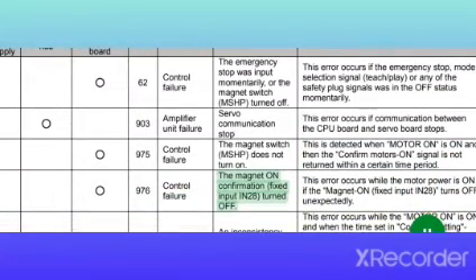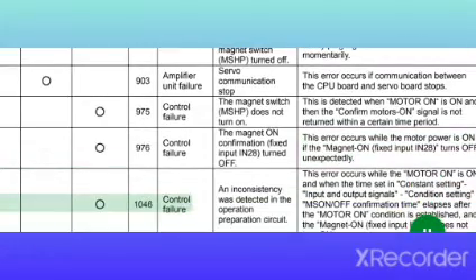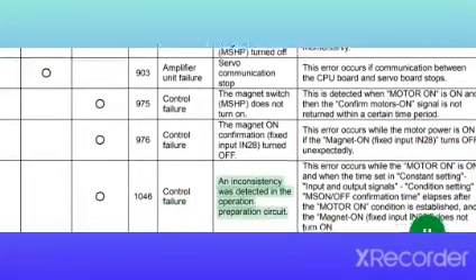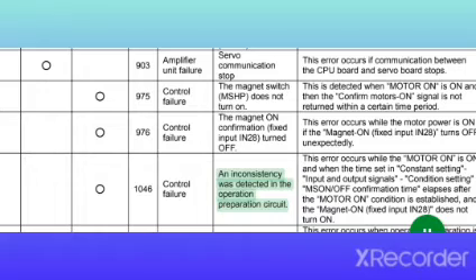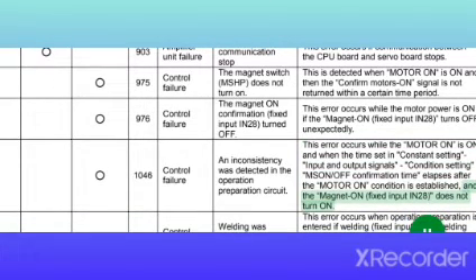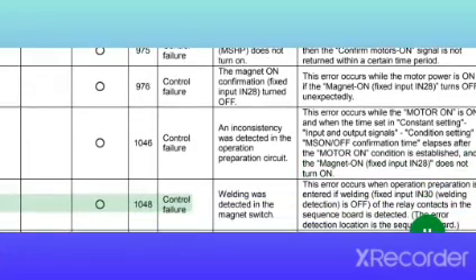The magnet on confirmation fixed input in 28 turned off. This error occurs while the motor power is on if the magnet on fixed input in 28 turns off unexpectedly. 1046 control, failure. An inconsistency was detected in the operation preparation circuit. This error occurs while the motor on is on and when the time set in constant setting, input and output signals, condition setting, MSON/OFF confirmation time elapses after the motor on condition is established, and the magnet on fixed input in 28 does not turn on.